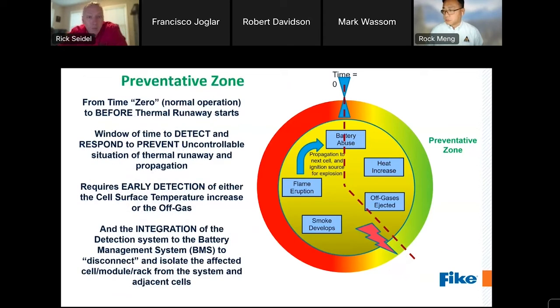The preventative zone is our window of time to detect, respond, and take measures to prevent an abused cell's clock from getting to thermal runaway. Detection of pending failure is achievable by precise monitoring of the surface temperature of the cell, or by detecting the off gas that is ejected by the cell during its initial buildup to thermal runaway, and subsequently integrating those signals with the battery management system, or BMS, to disconnect or isolate the affected cell or rack from the overall system or loop.